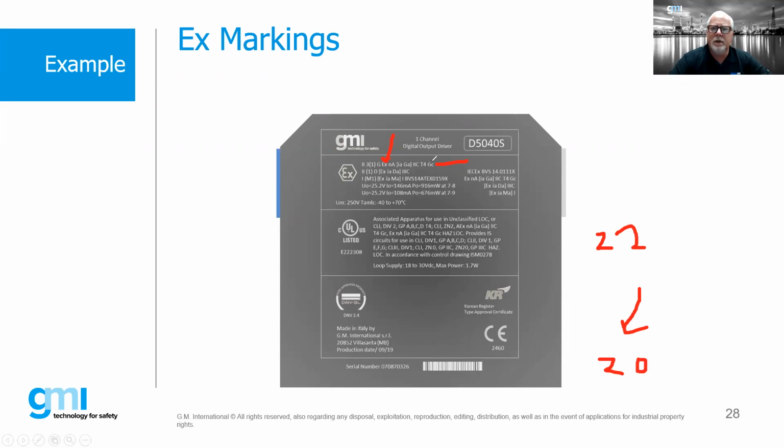Okay, that's the marking string that you would typically find on an intrinsically safe barrier. This is the marking string for dust. This is the marking string for mining applications. And then, of course, these are the parameters. On the North American side, it's rated to be installed in a Division 2 area or a Zone 2 area. And then it's also providing protection, and in the NEC world it would be marked in the same fashion, to where it can actually be installed or provide protection into a Zone 0, and it also can provide protection into a Zone 1. So there's a lot of information there that can be very confusing, but it's important to understand this marking when we're actually trying to select the product and do all this good stuff.